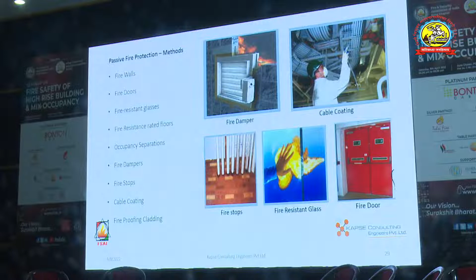So normally I've seen that they use only tempered glass and they don't use laminated glass. It is only laminated glass which will hold the glass in the frame. Except laminated, no other glass will hold the glass in the frame. This is very important because if the glass breaks, the firefighter below cannot fight because the glass panes start falling off from the window due to heat. So laminated glass is extremely important to be used. Of course, walls, doors, there's much to talk about.